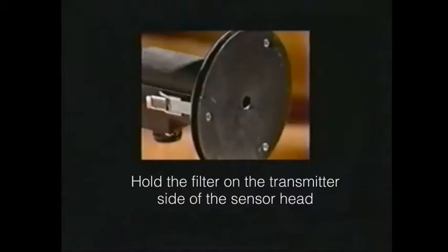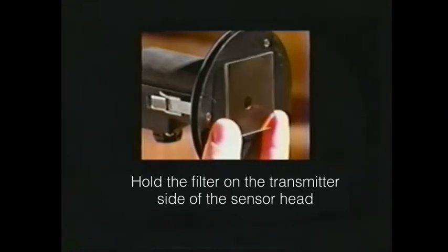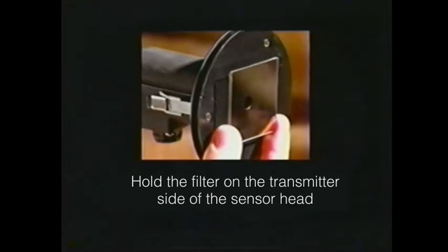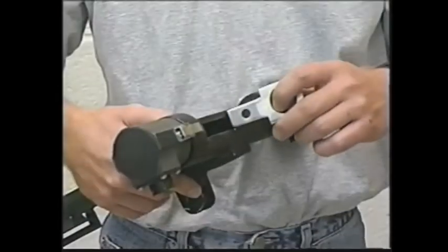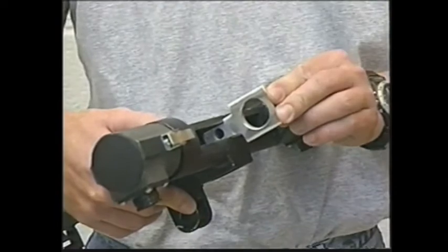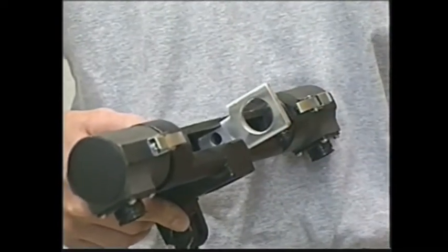Start the unit. Wait until the unit cycles to the test sequence. Check the results. For the partial flow head, insert the filter holder into the notch on the back of the head.